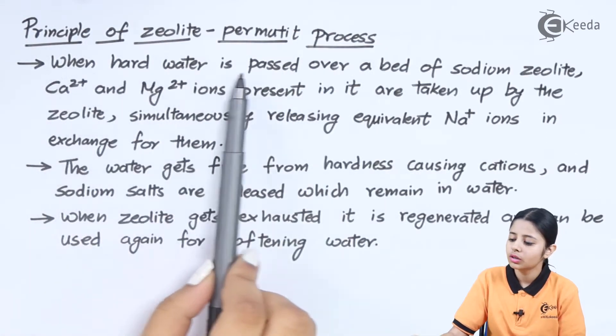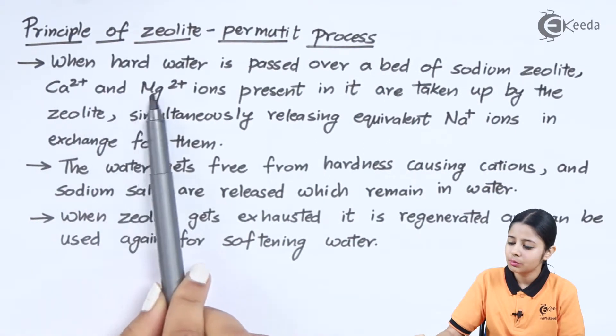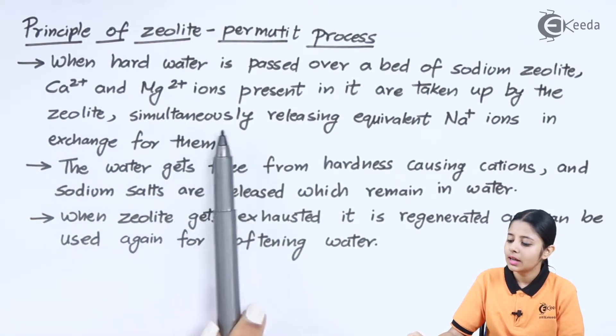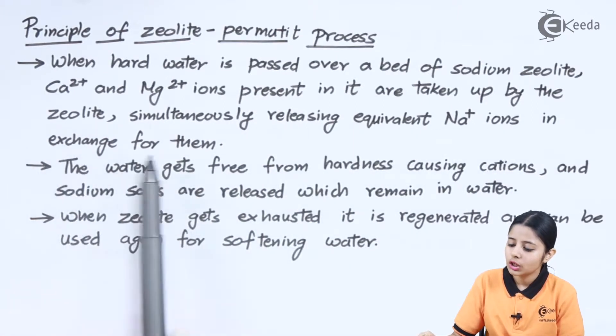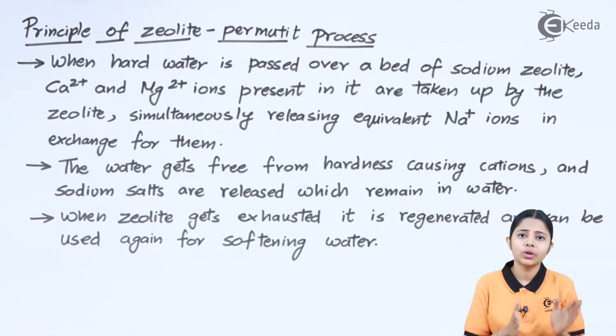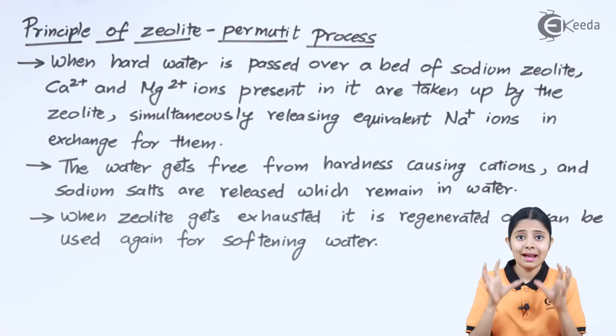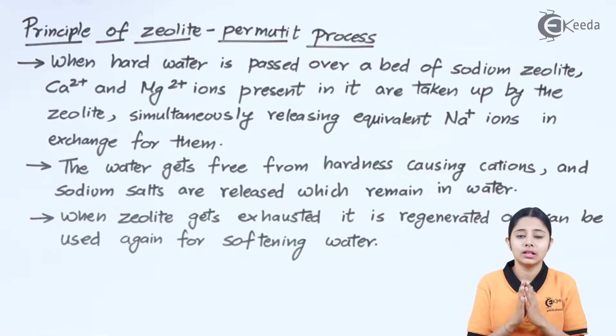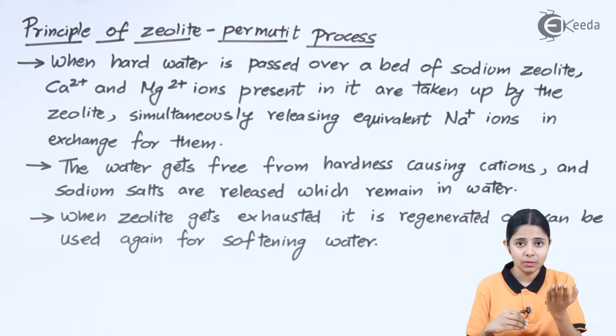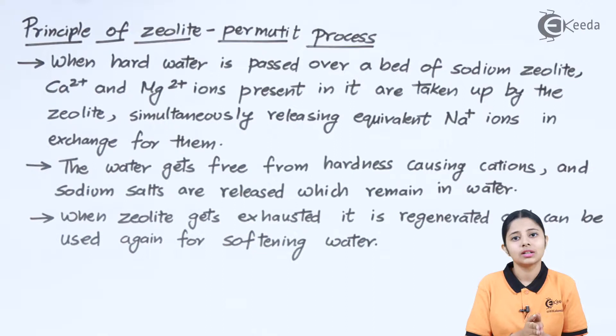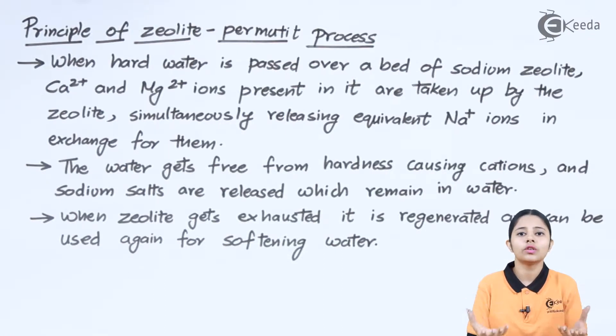The principle of the zeolite permutite process: when hard water is passed over a bed of sodium zeolite, Ca2+ and Mg2+ ions present in the water are taken up by the zeolite, which simultaneously releases equivalent Na+ ions in exchange. Hardness of water is due to carbonates or bicarbonates of calcium and magnesium — so the zeolite gives away its sodium ions and in exchange takes the calcium and magnesium ions. This give-and-take exchange is exactly why it is called an exchange process.